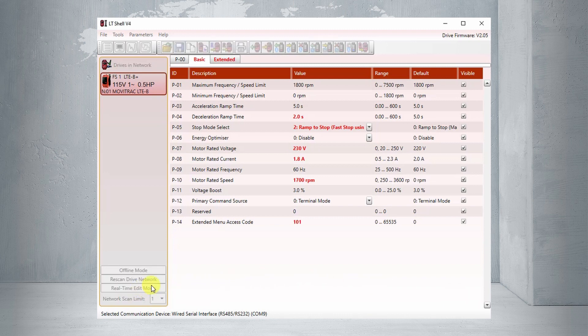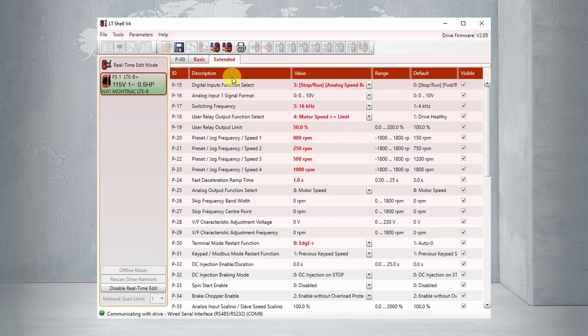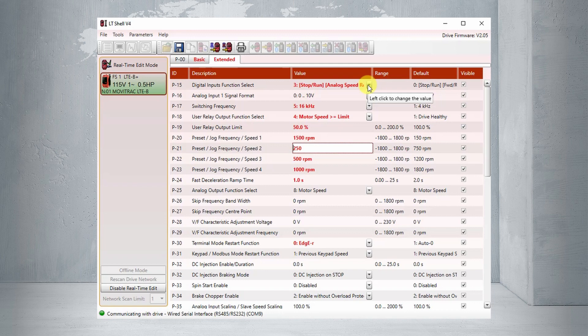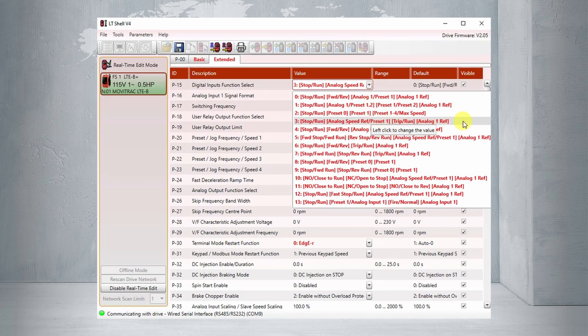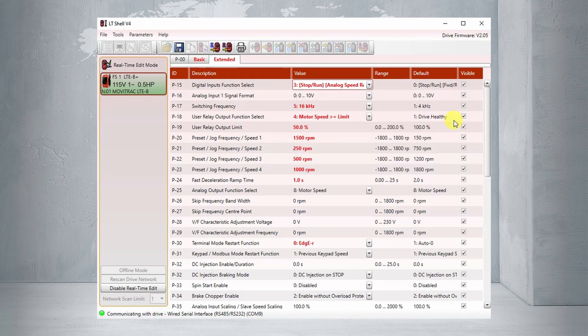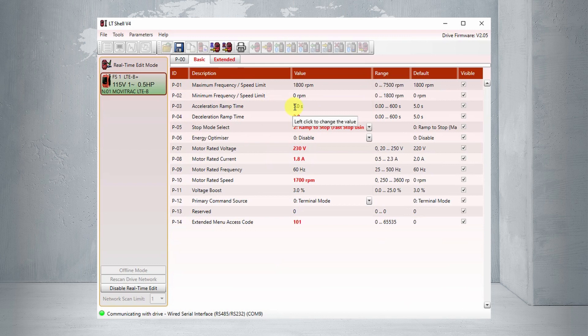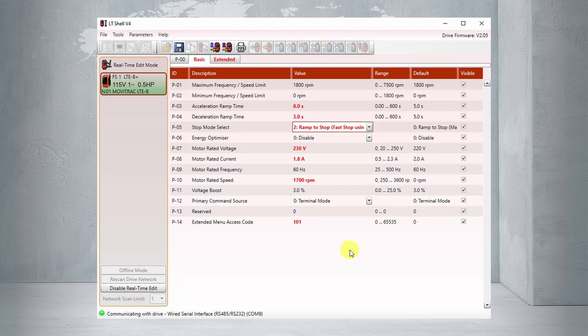First, I'm going to turn on real-time edit and make a couple of changes. Going to the Extended tab, I'll change Preset 1 to 1500 RPM. We're in Terminal Control mode with Variant 3. Digital Input 1 is the stop/run signal; Digital Input 2 selects between the potentiometer and the preset speed; Digital Input 3 is an external fault sensor; and the fourth input is the potentiometer. We're mostly going to use the preset speed at 1500 RPM. On the Basic tab, I'll change the acceleration ramp to 8 seconds and the deceleration ramp to 3 seconds. Since we're ramping from 0 to 1500 and back, these will be the actual execution times. I'll turn off Real-Time Edit and bring up the scope by clicking the Scope tab.